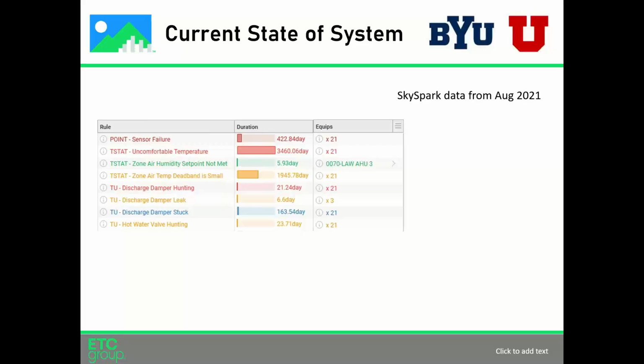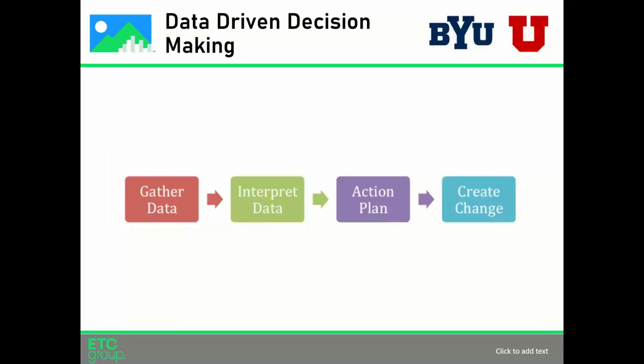One of the main ways we approached this was using data-driven decision-making. The process is: gather data, interpret data, create a plan, then act on that plan. ETC helped us filter through all the data points. A building like College of Law has a lot of data points and opportunities being created from there. Data-driven decision-making lets us exclude the bias of stories grown over years about the system not working, or relying on a customer to complain before acting, and really allowed us to focus our efforts, which we used primarily for our zone occupancy lighting control system.